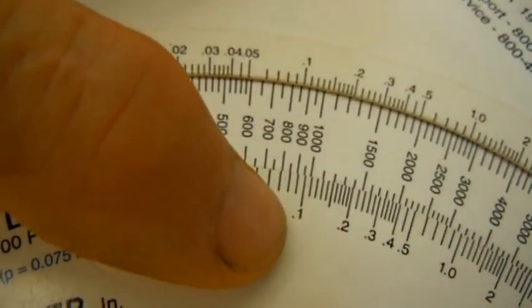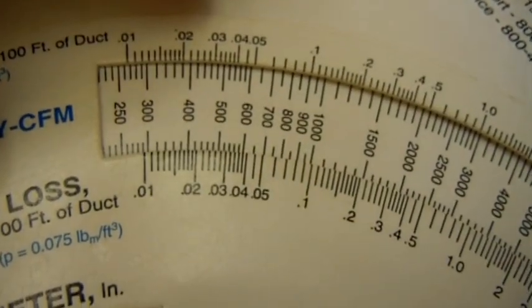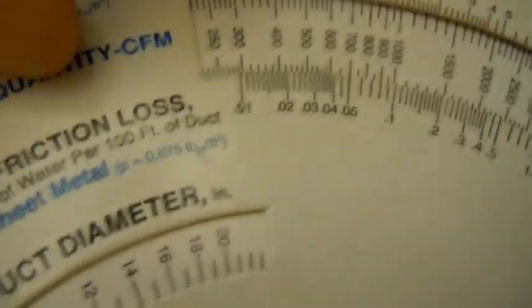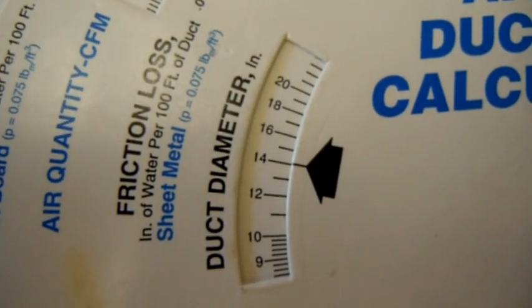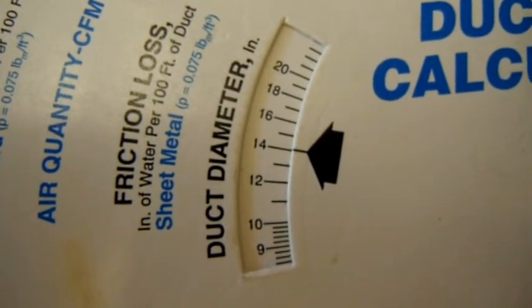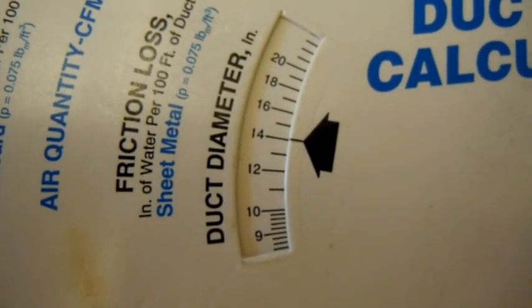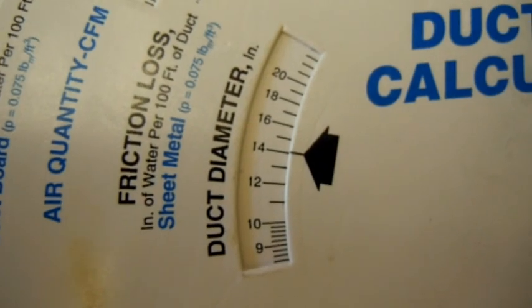So at .1, we'll line this up to a 2.5 ton air conditioning system. That would be 1,000 CFMs at .1. And that would line up the round duct diameter to be about 14 inches. And that would be what you would need off from the plenum.